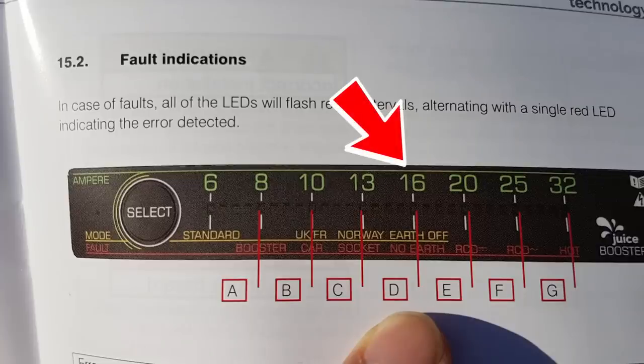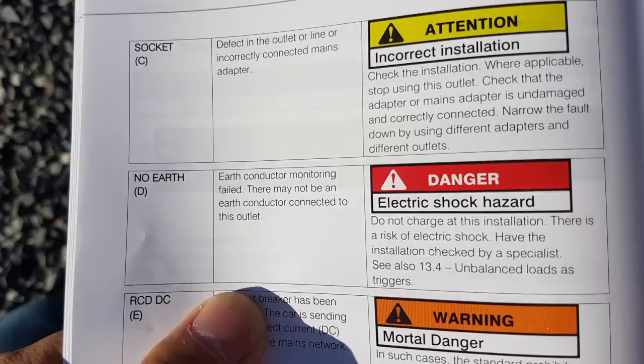Looking at fault D, the 'no earth' default: it says 'earth conductor monitoring fail — there might not be an earth conductor connected.' It has a danger symbol with a red electric shock warning. I realized I'd been charging on this for a while — lucky I didn't get electrocuted! It says 'do not charge at this installation, risk of electric shock.' That made me unsure, so I didn't try to push it to charge — I trusted the equipment.